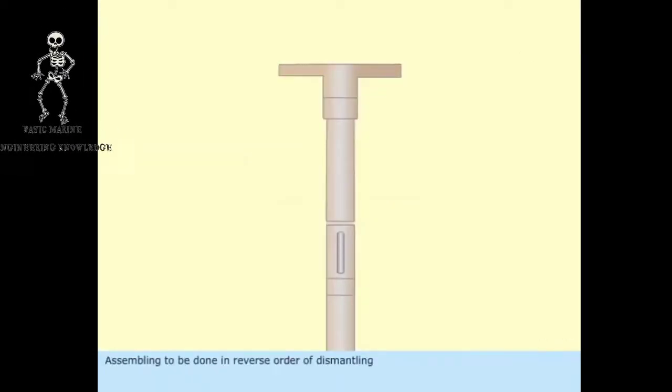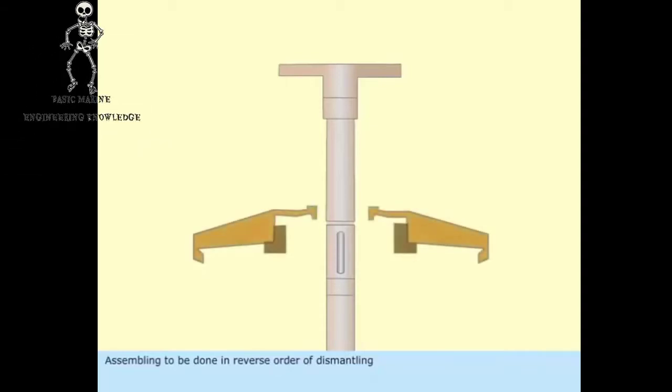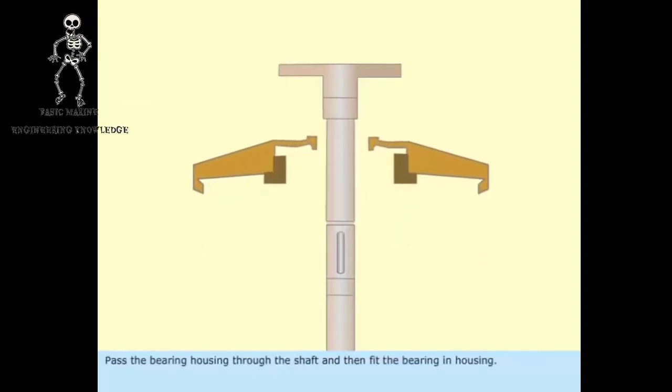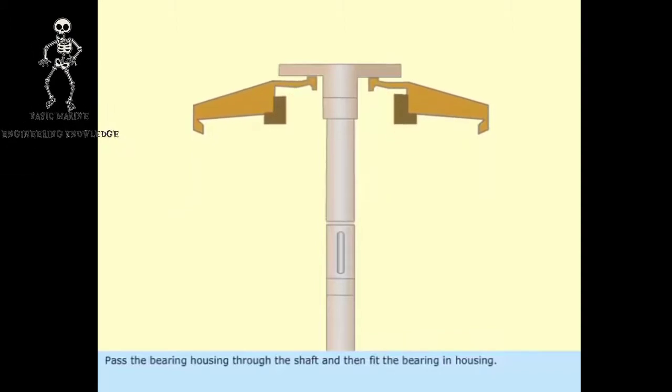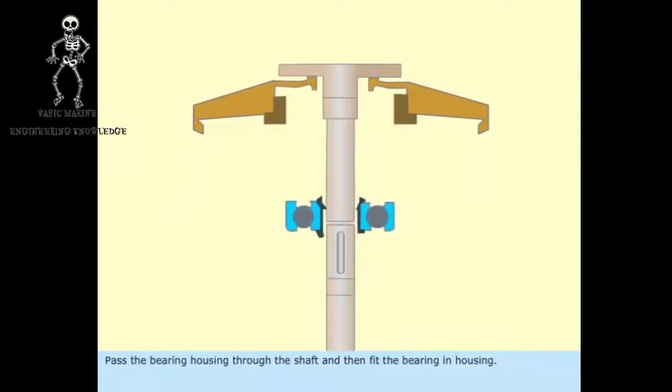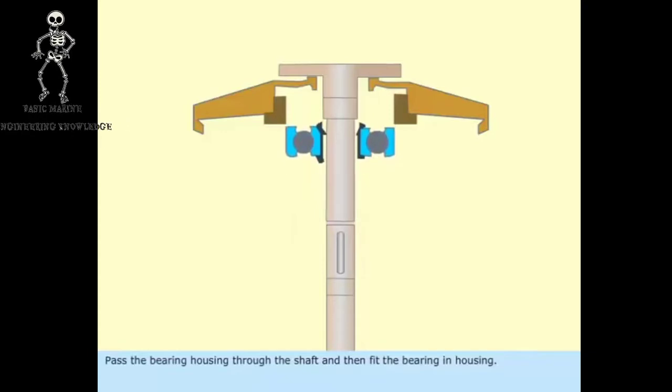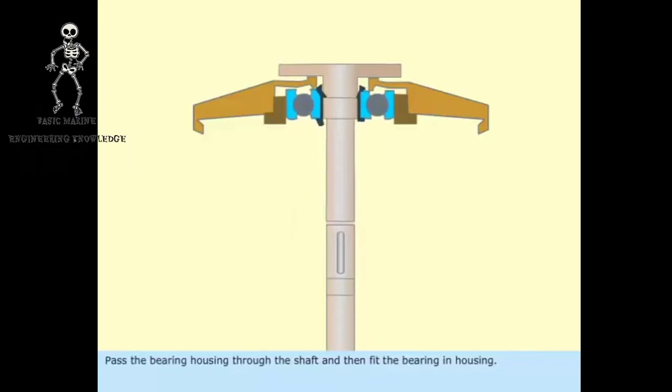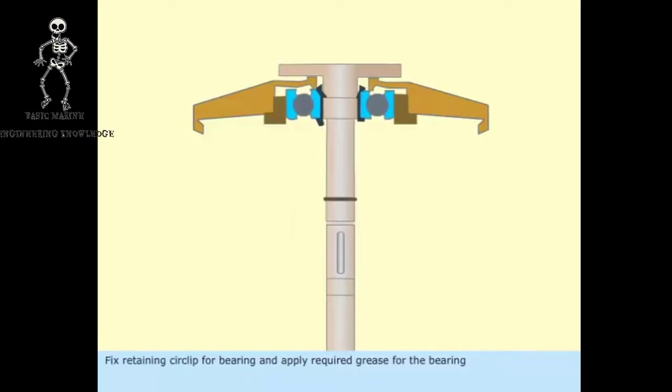Assembling to be done in reverse order of dismantling. Pass the bearing housing through the shaft and then fit the bearing in housing. Fix retaining circlip for bearing and apply required grease for the bearing.